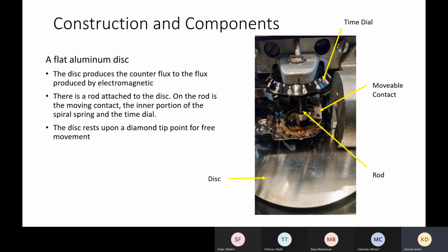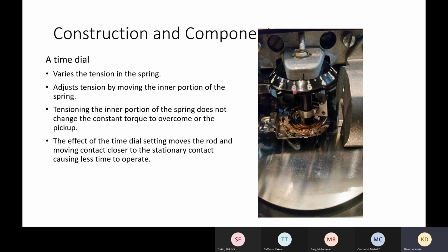And then we have the time dial. So the time dial adjusts what position this movable contact is in. The lower the number, the closer this movable contact is to the stationary contact. The higher the number, the farther this movable contact is away from the stationary contact.